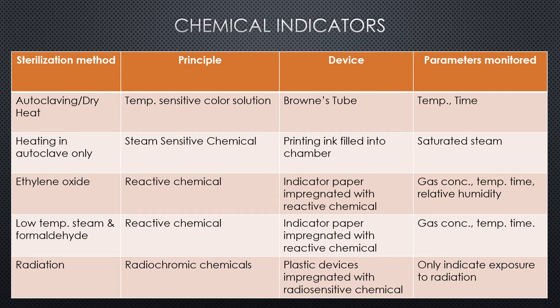Here are some examples of chemical indicators for monitoring the sterilization process. First is autoclaving or use of dry heat. The basic principle uses a temperature-sensitive color solution. The device is a Browne's Tube — sealed tubes partly filled with a solution that changes color at elevated temperature. The rate of color change in proportion to temperature is measured, and the parameters monitored are temperature and time. When considering heating in an autoclave only, a steam-sensitive chemical is used.